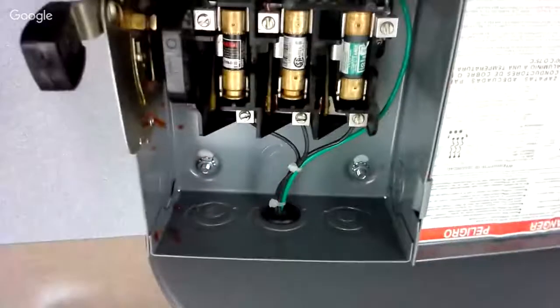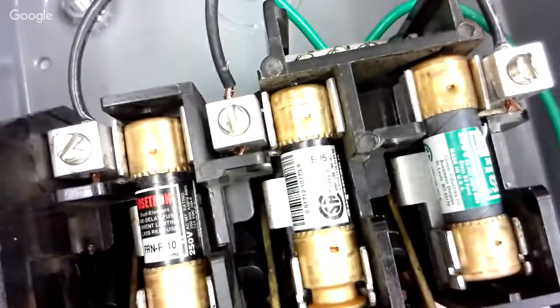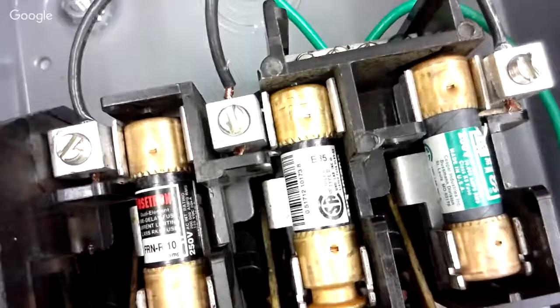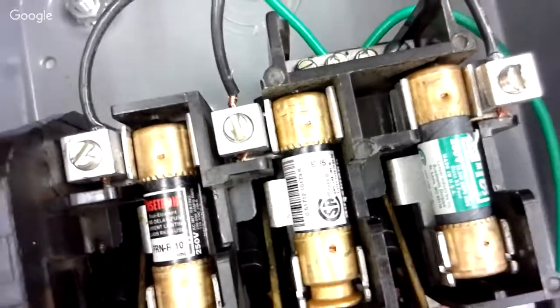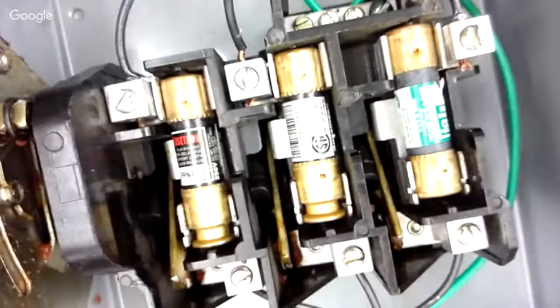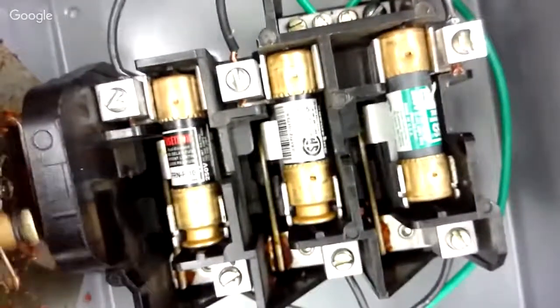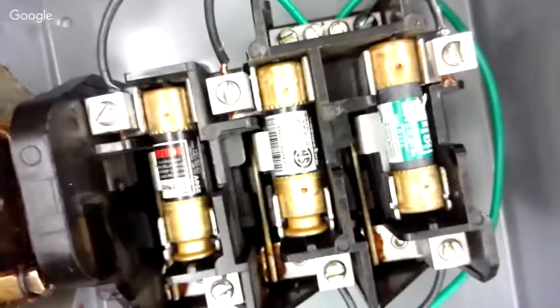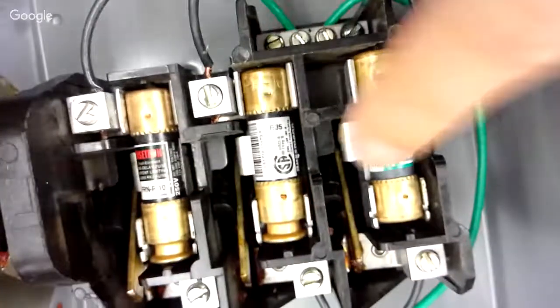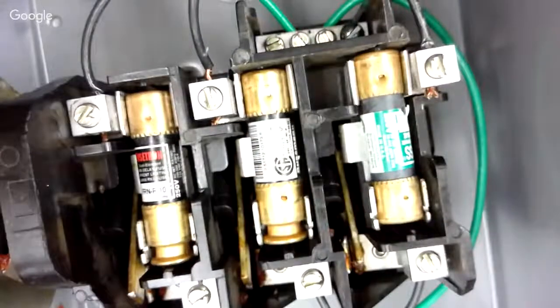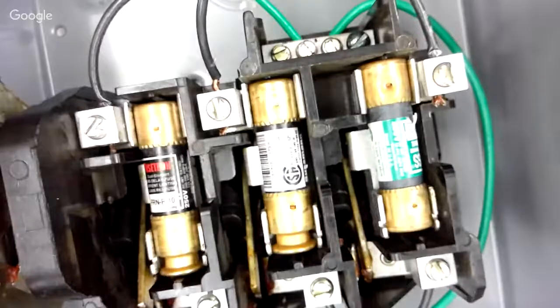Notice that inside this disconnect are fuses. And if you look right here is a blade. You'll see a blade right here. And that blade is controlled by this handle. See the switching action of that blade? That switching action, and you'll see some little lubricants. If those don't engage correctly, that's going to cause an overload when we try to fire this up. But we're going to pull a fuse out and test it.